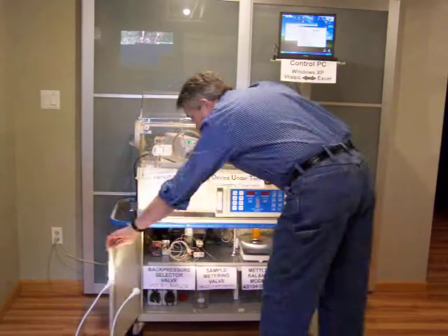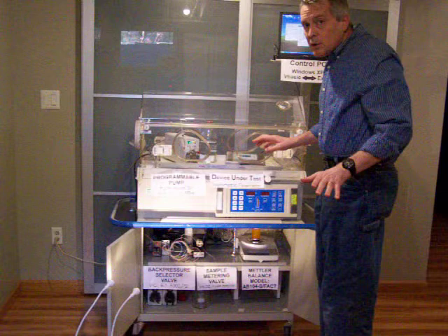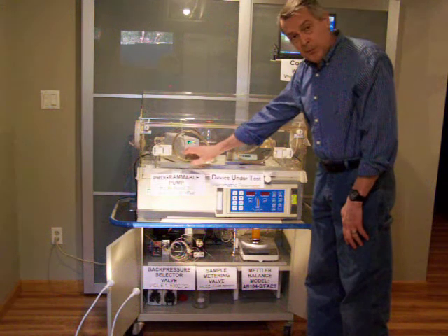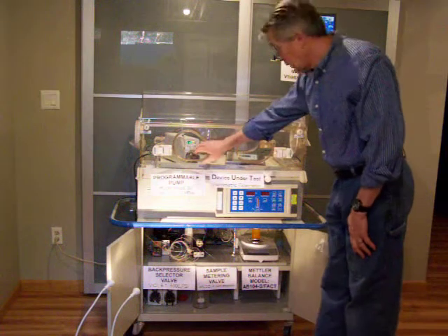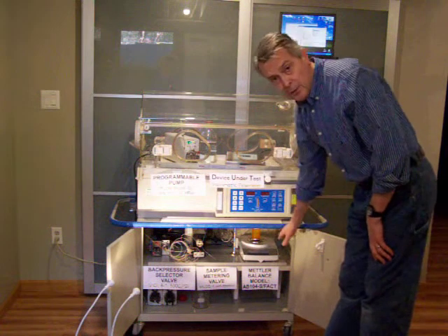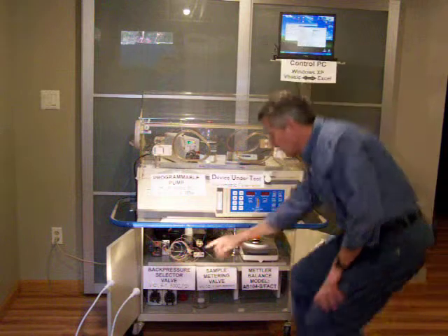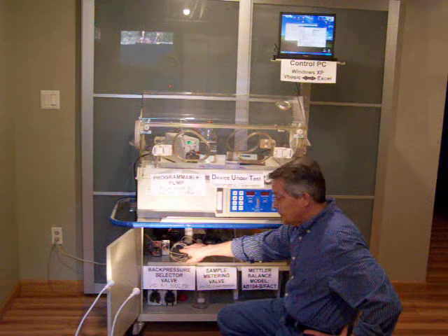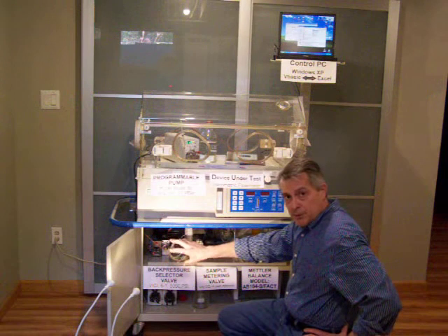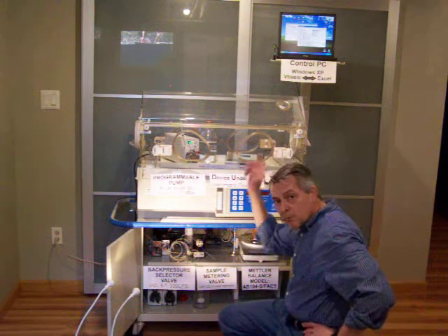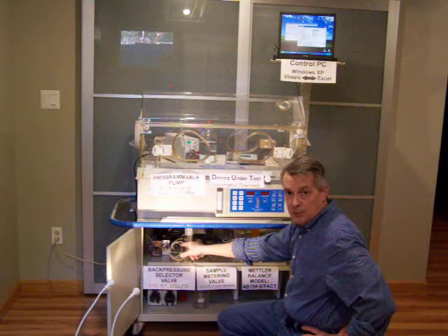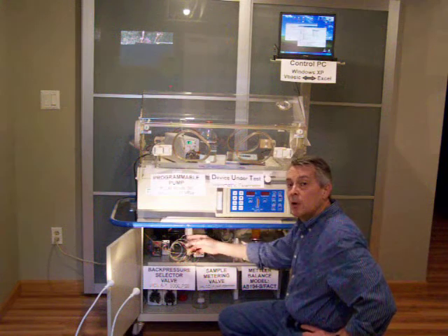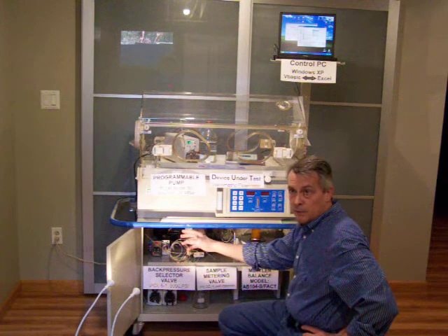Underneath here are the real stars of the show, so to speak. When fluid is delivered from the pump through the device under test, or it can be delivered from the pump directly to the measuring apparatus, it first passes through a 6-port high pressure injection valve, which allows, by RS-232 from the computer, selection of a tubing of an appropriate internal diameter and length, such as to provide a back pressure coefficient for any given flow rate.